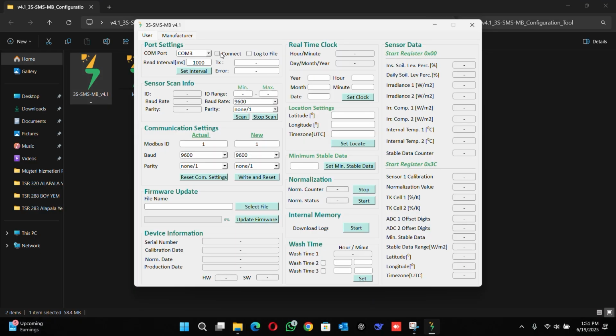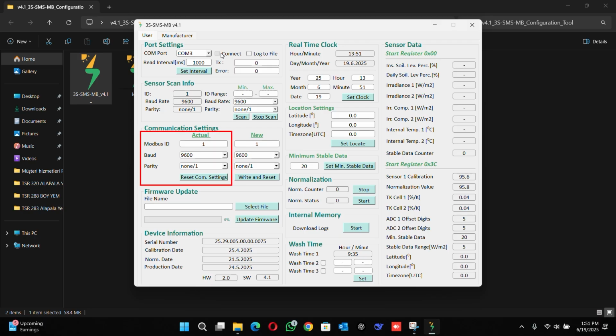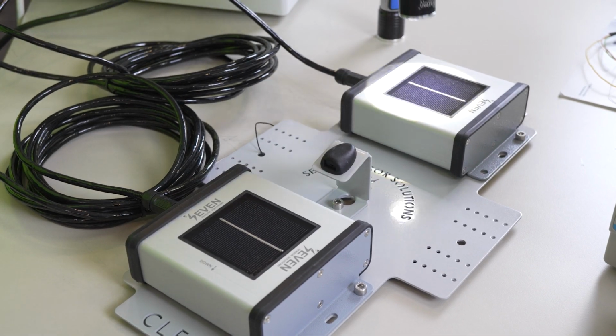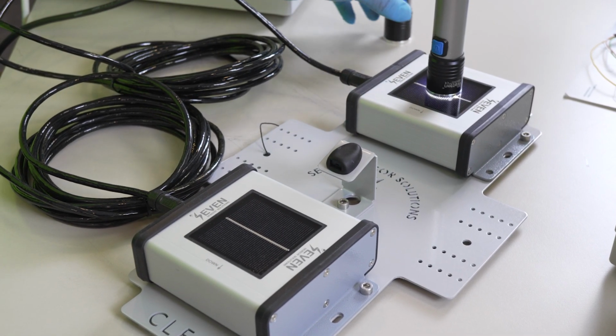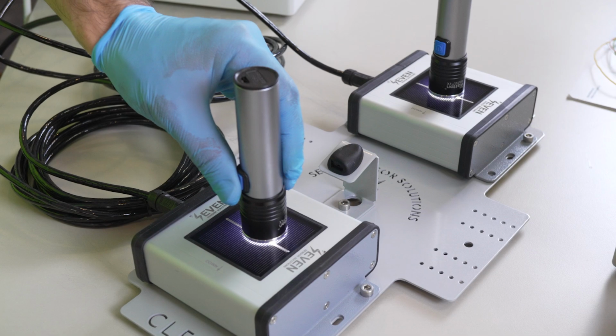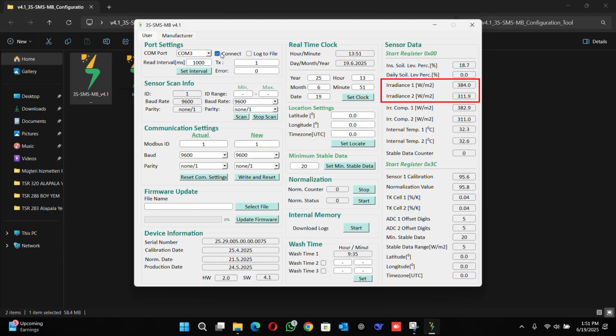Now connect using the default Modbus parameters. Device ID 1. Baud rate 9600. Parity none. Click Connect. At this point, you can check irradiance readings with a light source to ensure the sensors are active.